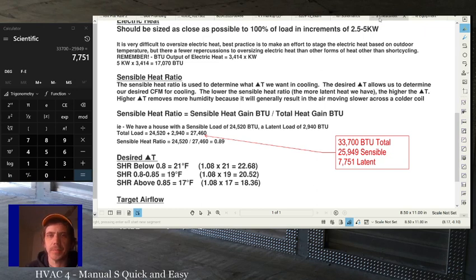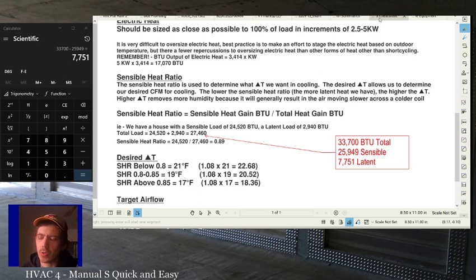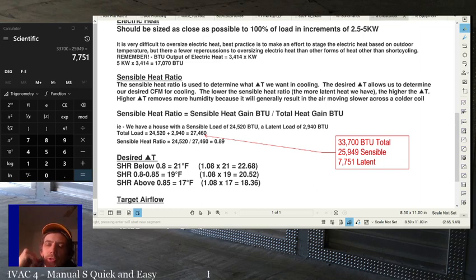The last tip I can give you is, if you're replacing equipment and you want to go that extra mile and you're not doing a load calc, right? Really, if you're replacing equipment, you should always do a load calc. But I know in the real world, not many people are going to do that. So the only other pro tip I can give you is, if at all possible, look up the original expanded cooling data for the equipment that you're replacing, if it's available. And if that's available, you can try and match the new equipment to the original cooling data.